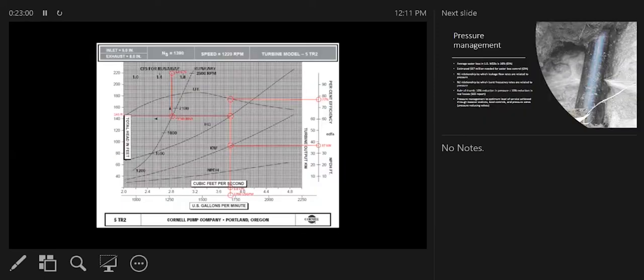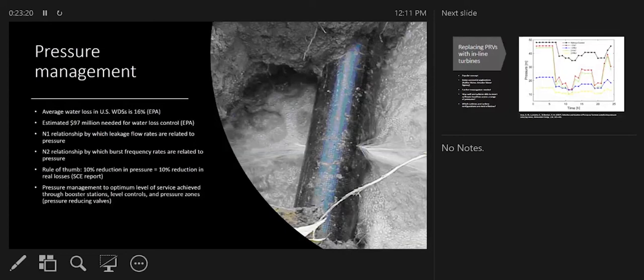This is just an example of a characteristic and efficiency curve, and this is how turbines are selected. Basically, you're selecting a turbine based on one target head and one target flow, which can be a problem if you have a huge variety of flows that you're dealing with at your site.